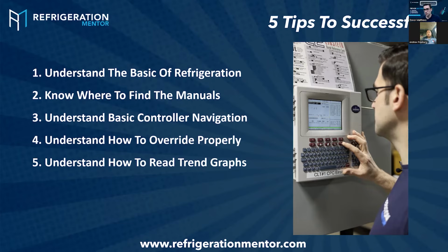You could really go in and figure out if your case superheat is wrong just by a graph. You pull it up and you look at it, and you've got a couple degrees off on one case, let's say. You graph it out and you can see the trend is normal, then all of a sudden it gets a little longer, takes a little longer to pull down that case. So what could that be? Probably the filter in the TXV is starting to plug up, causing it to take longer and longer to pull down that case.